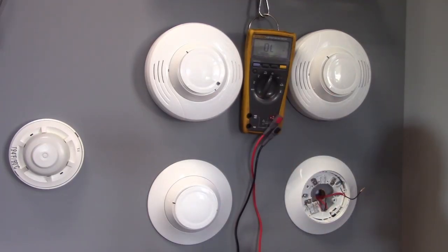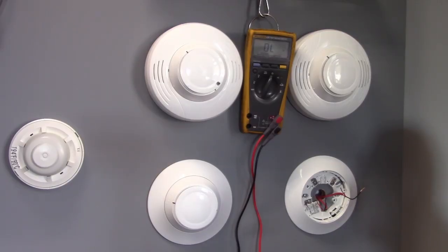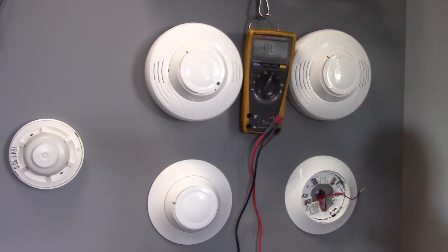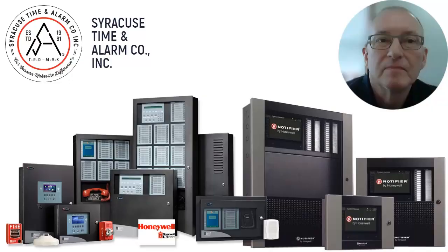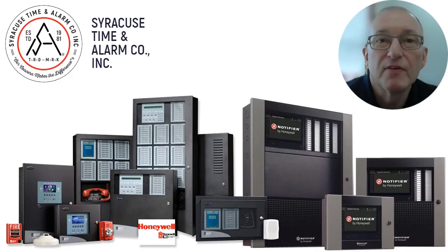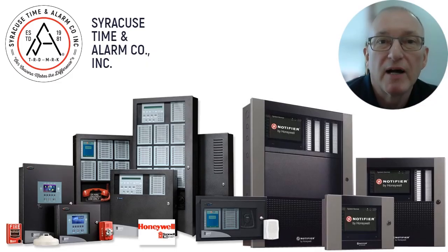Pay attention to what detectors are online and offline. If you have a computer hooked to the fire panel, you can typically, if you can remote into it, you can see what devices are missing and that will tell you which way to go. We hope that you found this video to be helpful and informative. Please like and subscribe for more content.